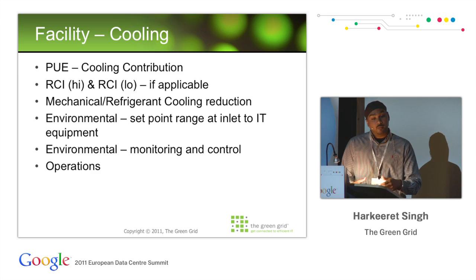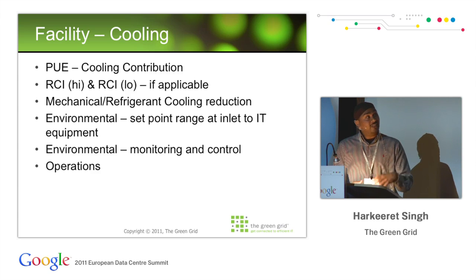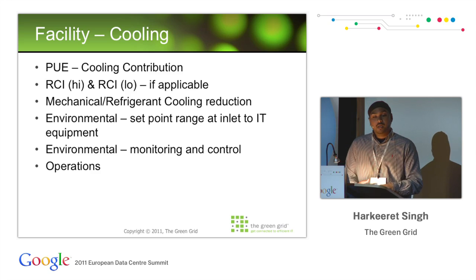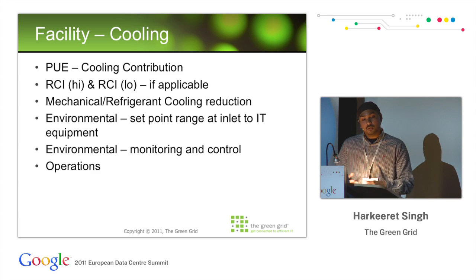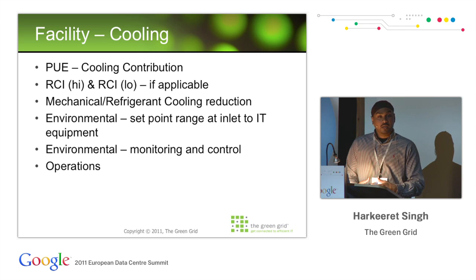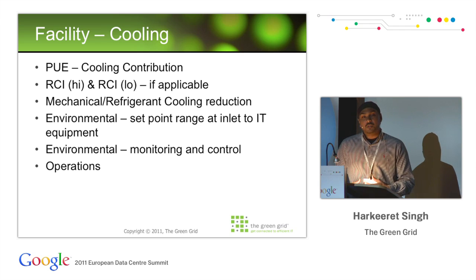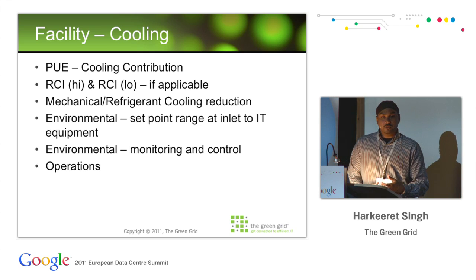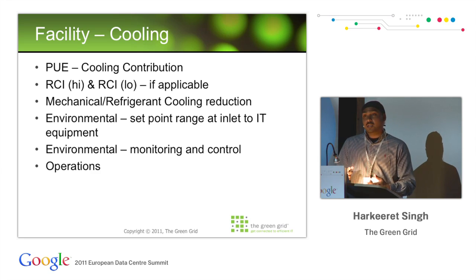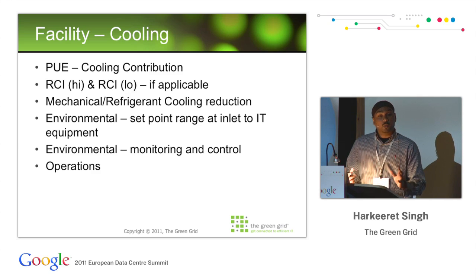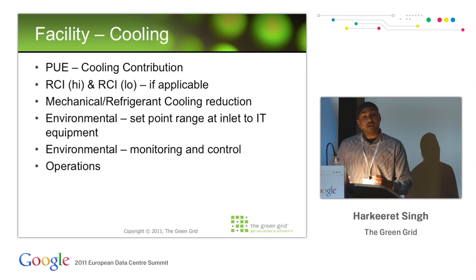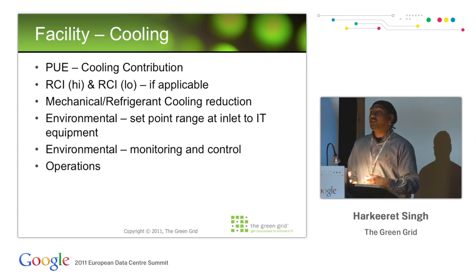We then move on to mechanical refrigerant cooling reduction, and we've been very specific with the words used here. What we're most interested in is reducing the amount of mechanical refrigerant cooling. How you do that is entirely up to you - whether you use air side economizers, water side, whether you open the doors and windows and use filters, whether you use liquid cooling to the rack or to the server. What we're most interested in is reducing the hours you're using mechanical and refrigerant cooling, and also we want to see some innovation.